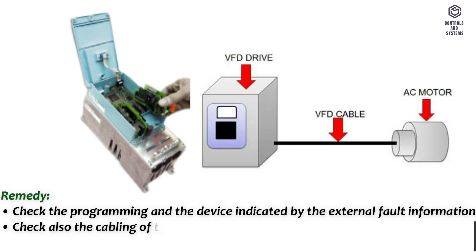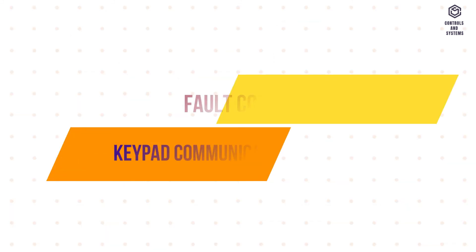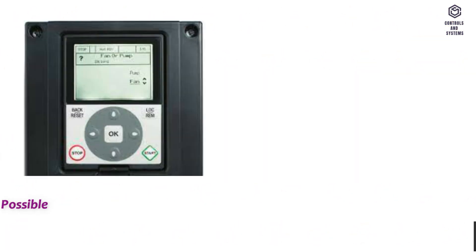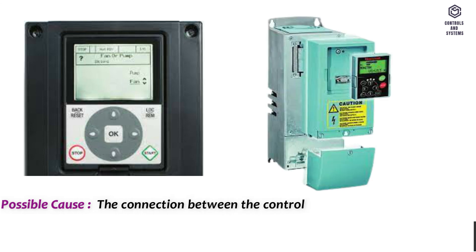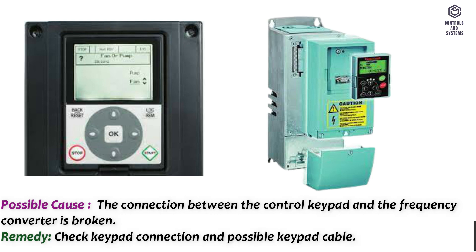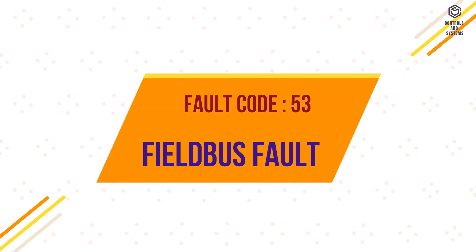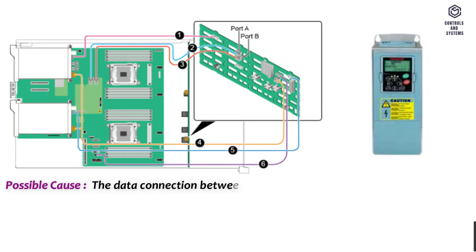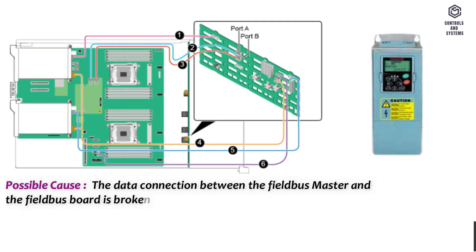Fault code 52 – Keypad communication fault. Possible cause: the connection between the control keypad and the frequency converter is broken. Remedy: check keypad connection and possible keypad cable. Fault code 53 – Field bus fault. Possible cause: the data connection between the field bus master and the field bus board is broken. Remedy: check installation; if installation is correct, contact technical support.